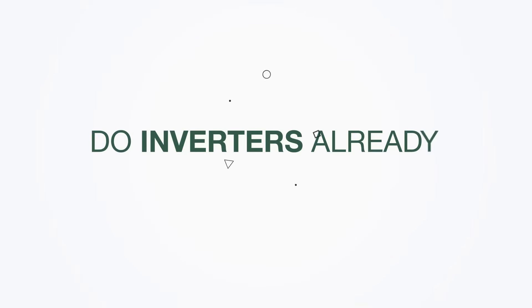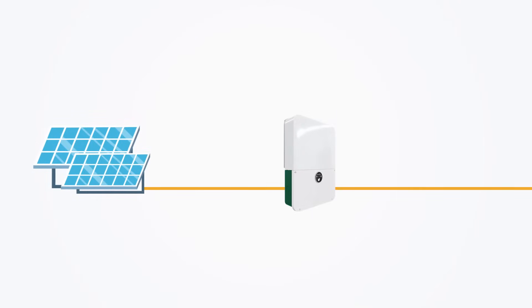Do inverters already take care of this? Inverters can prevent energy generated by the modules from getting past the inverter. However, high voltage can remain between the modules and the inverter. As a result, most rapid shutdown codes require shutdown to occur at the module level, hence the common use of module-level power electronics to meet this function.